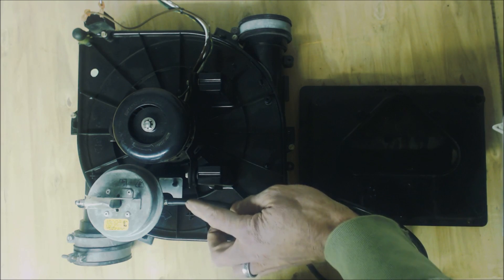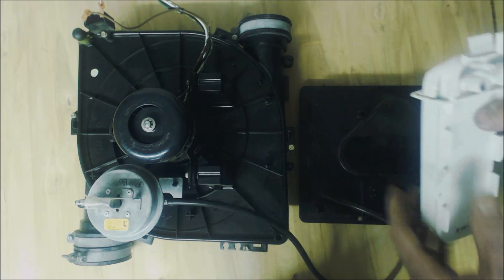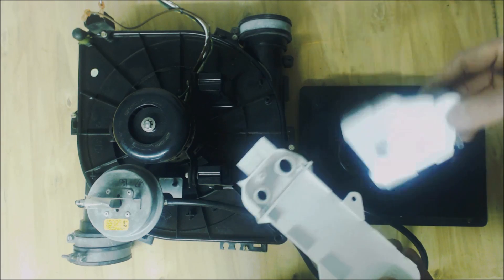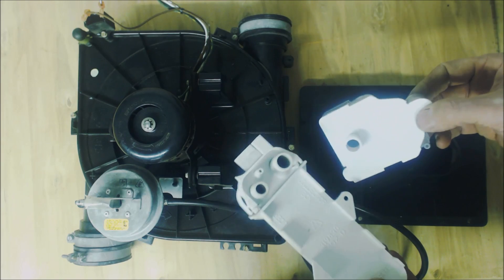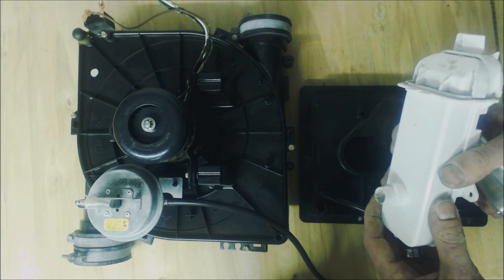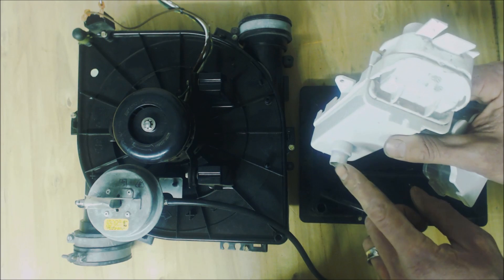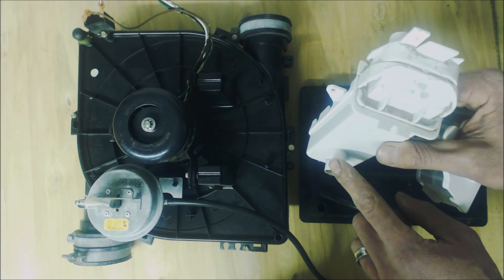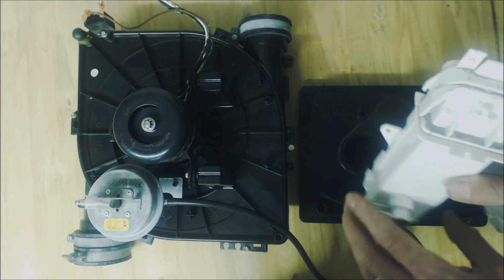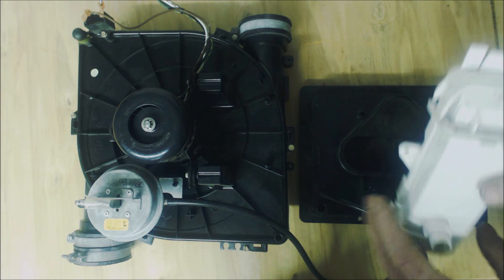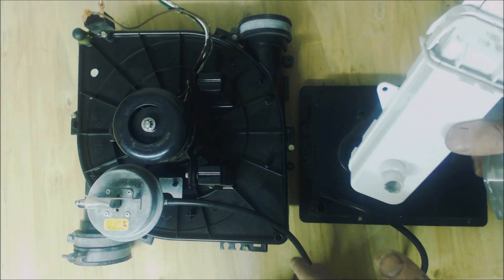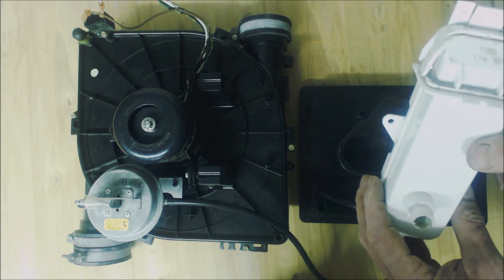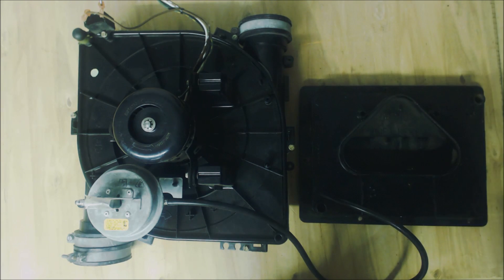You always make sure that your pressure tube is disconnected from your pressure switch before you apply any air compressor or anything to these traps and the condensate lines. You want to make sure as well that the condensate line that's attached to the trap is able to go downwards away from the furnace at about a quarter inch of pitch per foot or more and then get to a drain. So that's that.